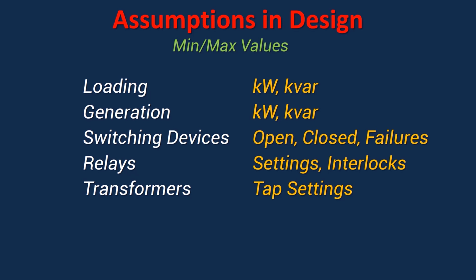It is important to mention that assumptions must be made during design. This means the design model is usually generated with minimum and maximum loading and generation values, and for very good reasons: for producing conservative results when doing equipment sizing, voltage drop, fault analysis, arc flash, device duty evaluation, etc.